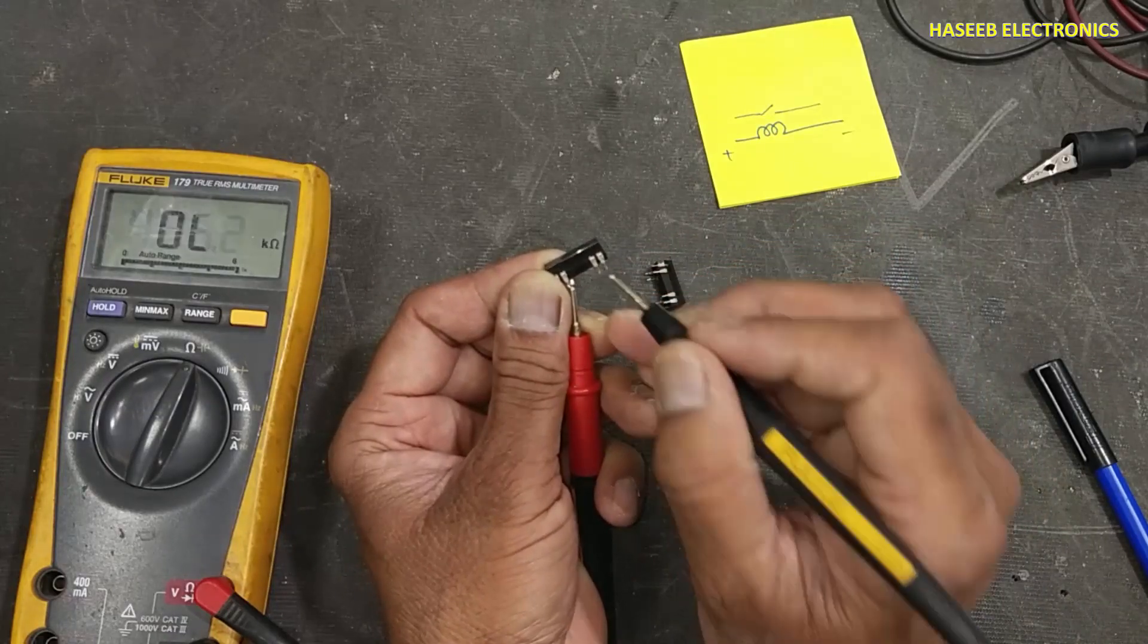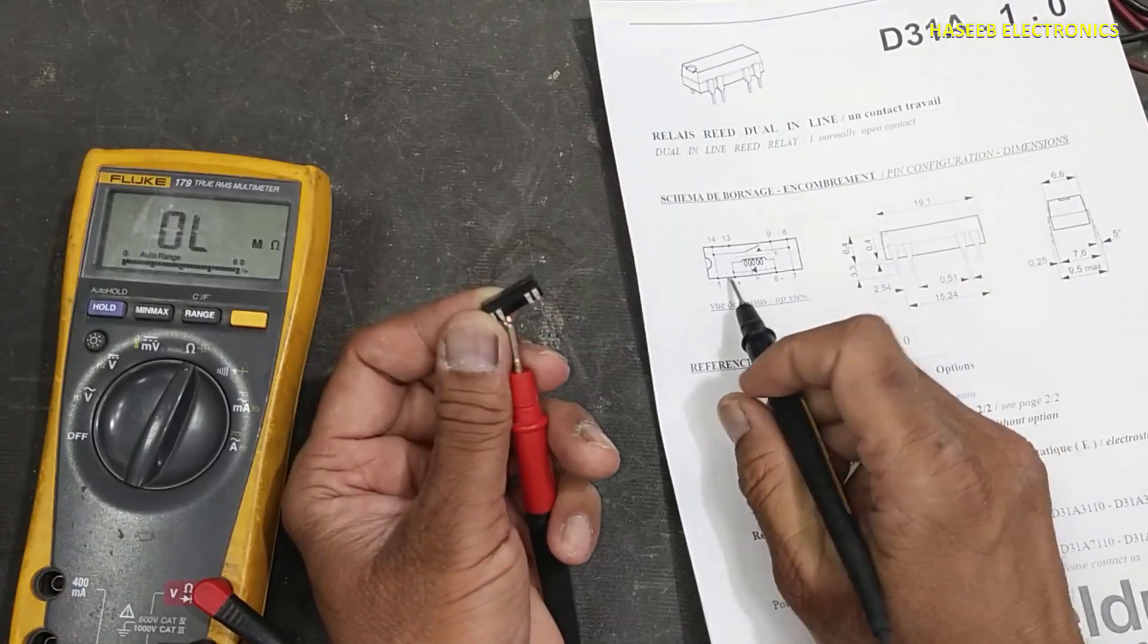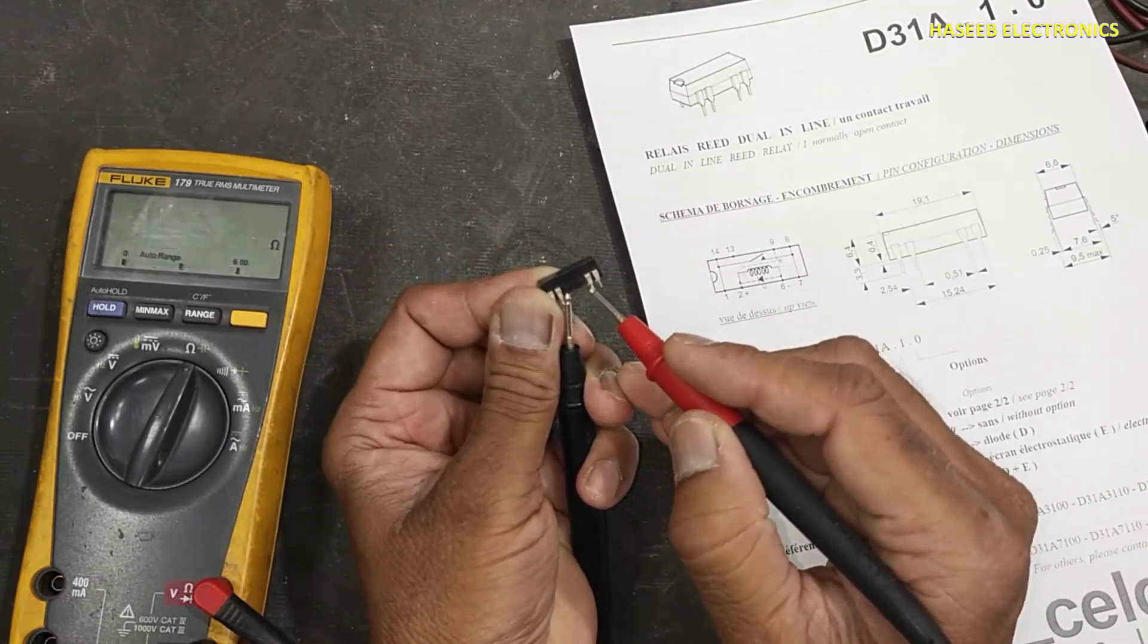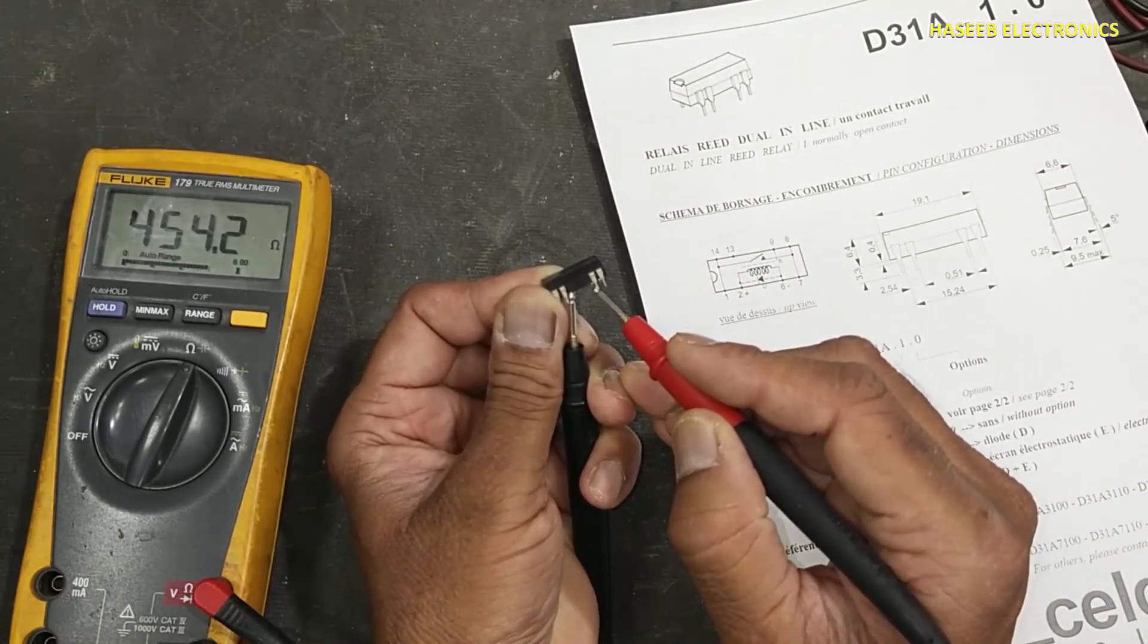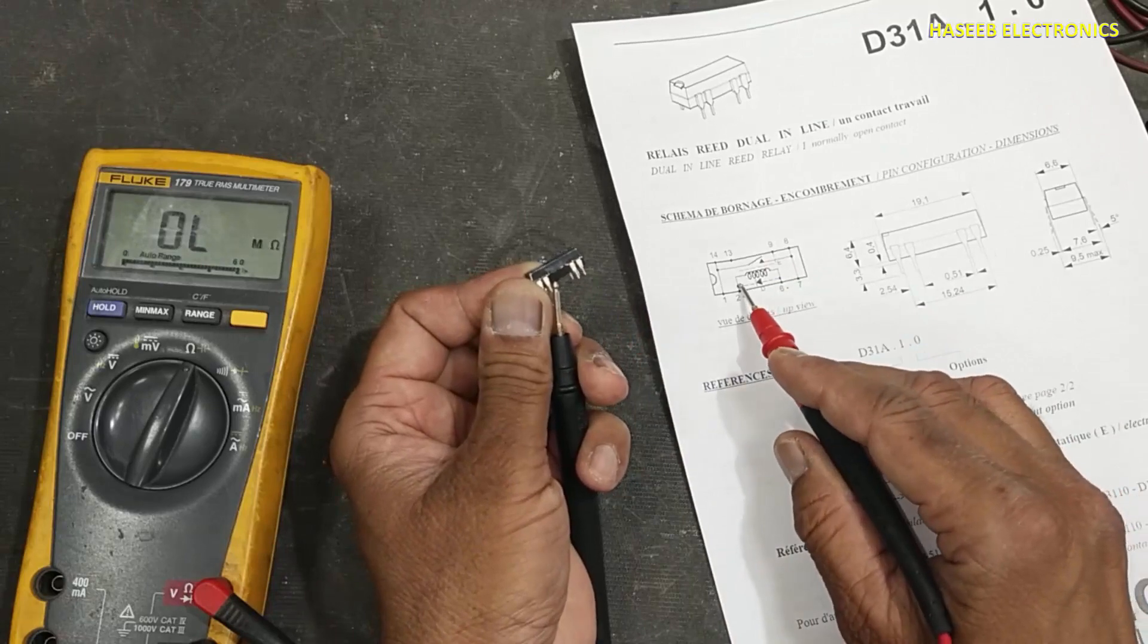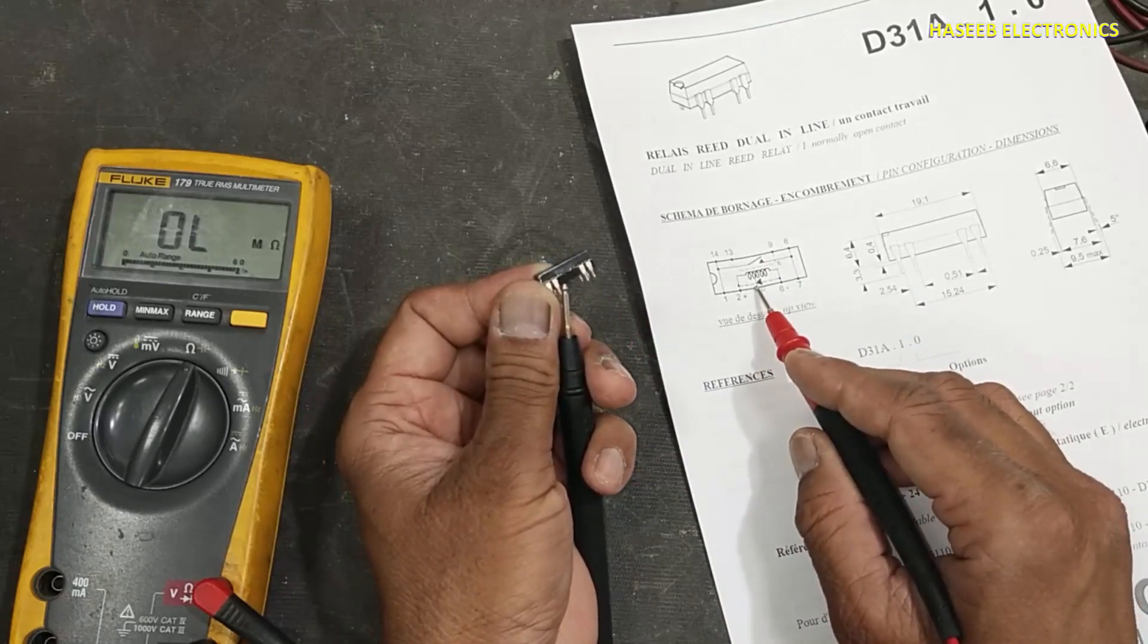485 ohms. On one side it will give coil resistance. If you reverse the leads at the same two points, it's giving 454. Why? One side will give diode drop voltage.